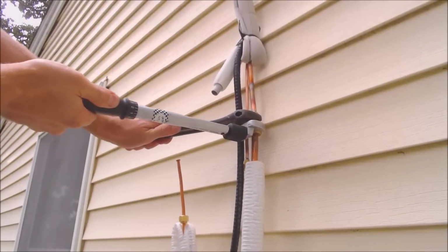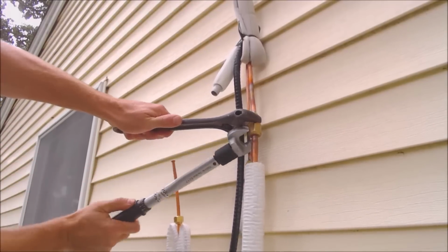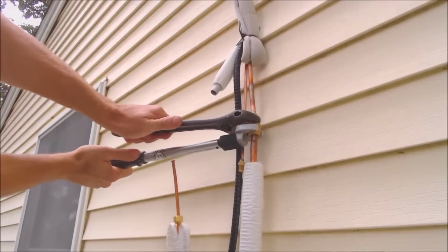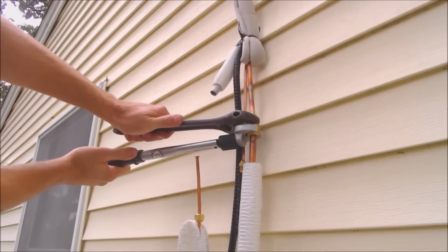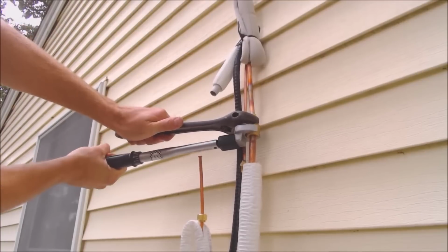And some manufacturers recommend two tightening torques, a lot of them are just one tightening torque. If they recommend two tightening torques, you tighten it to the first torque, then you loosen it. You adjust your torque wrench to a higher setting, usually around, say, 5% higher, and then you tighten it a second time. You want to make sure to follow the manufacturer specifications for their specific flare nut.